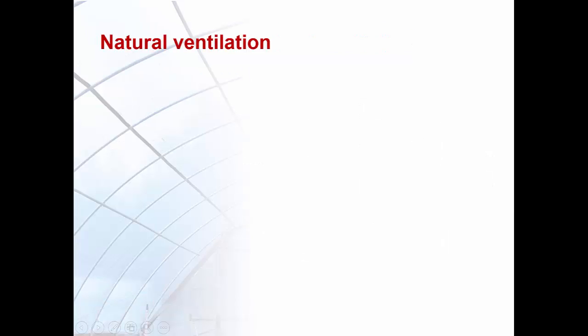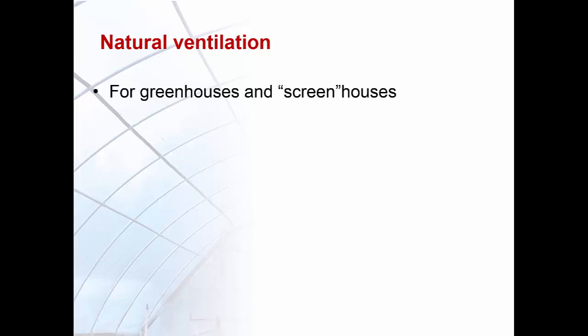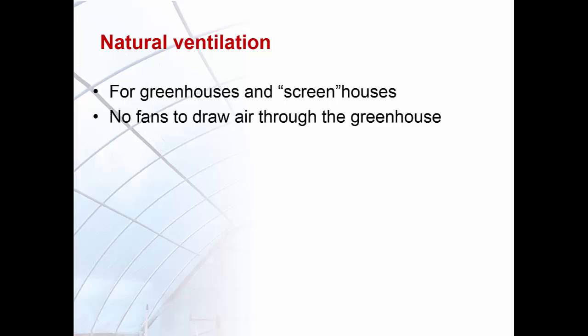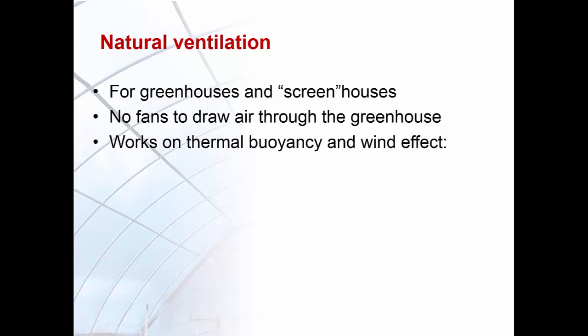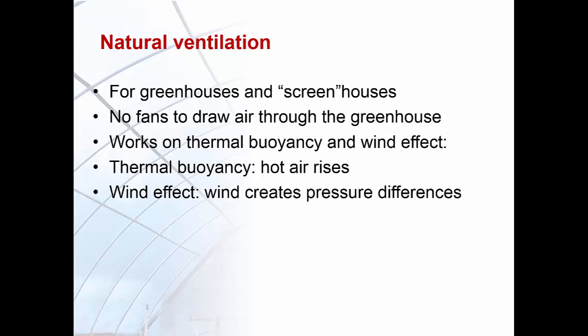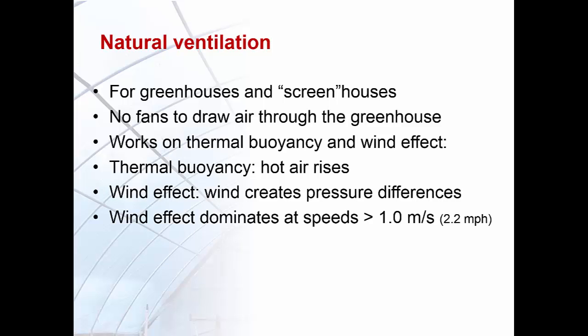Natural ventilation is the process of supplying and removing air through an indoor space without using mechanical systems. It refers to the flow of external air as a result of pressure or temperature differences. Used for greenhouses and screenhouses, these systems do not require fans. Natural ventilation works on thermal buoyancy and wind effect. Thermal buoyancy helps hot air rise due to reduced air density, while wind effect creates pressure differences. Wind effects usually dominate at speeds higher than 1 meter per second.